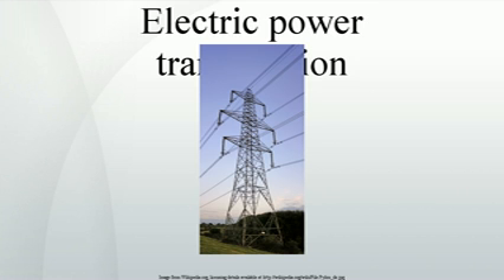HVDC is also used for submarine cables because over about 30 kilometers, 19 miles, lengths AC cannot be supplied. In these cases special high-voltage cables for DC are used. Submarine HVDC systems are often used to connect the electricity grids of islands, for example, between Great Britain and mainland Europe, between Great Britain and Ireland, between Tasmania and the Australian mainland, and between the North and South Islands of New Zealand. Submarine connections up to 600 kilometers, 370 miles, in length are presently in use.